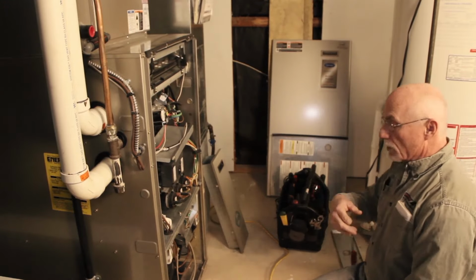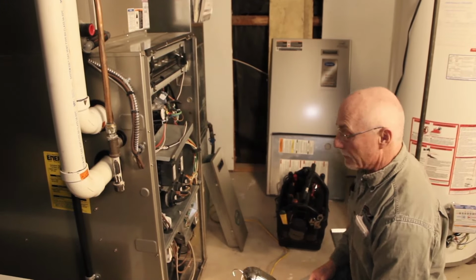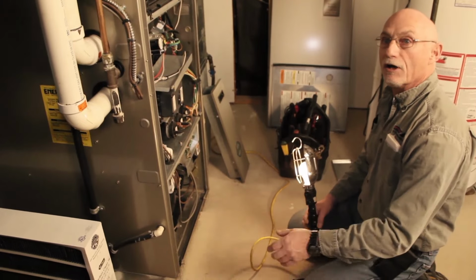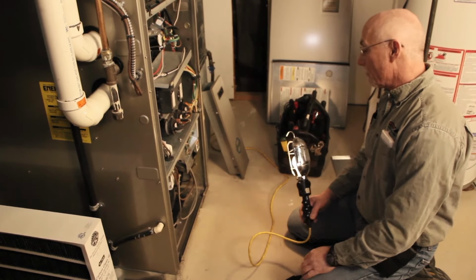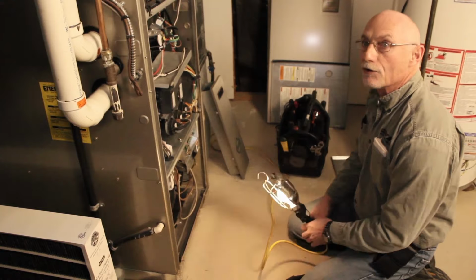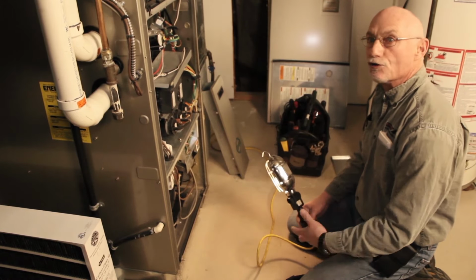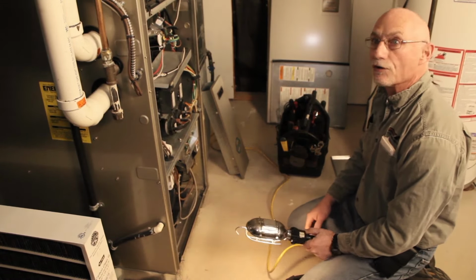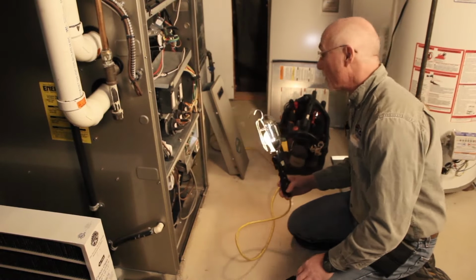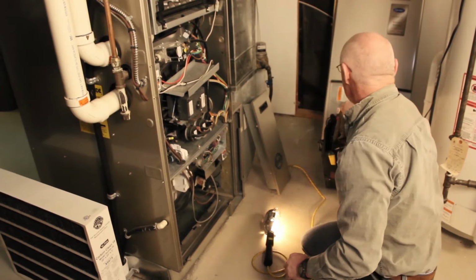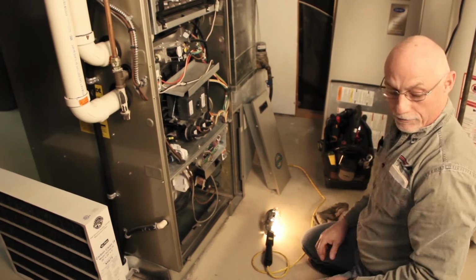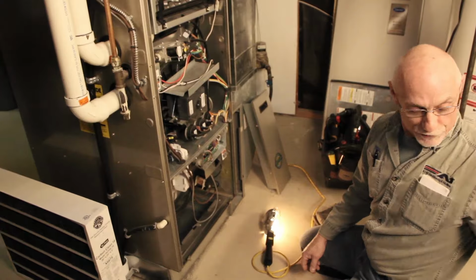Now to the blower, just to make sure that we don't have any dirt or dust that's accumulated in there that might affect the airflow coming through it, which if we slow the airflow down on these furnaces, it can cause problems with the heat exchanger overheating and eventually deterioration of the heat exchanger, prematurely you might want to say. So the next thing is I'm going to give it a cleaning. I'm going to be starting up my vacuum so don't let it scare you.